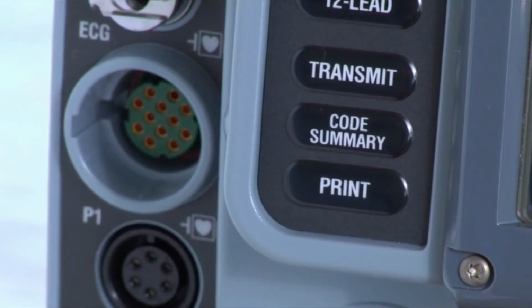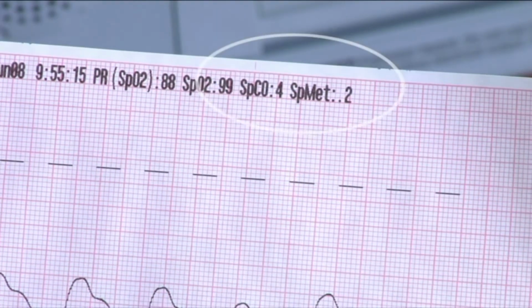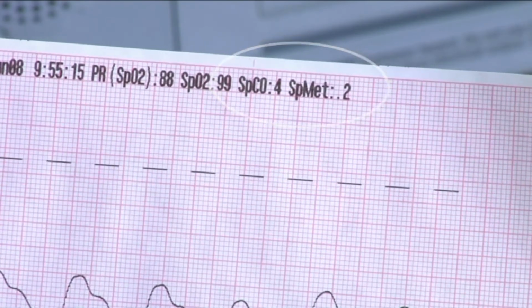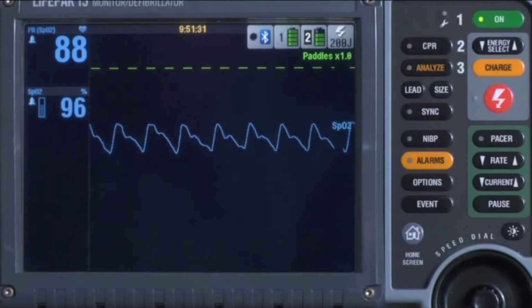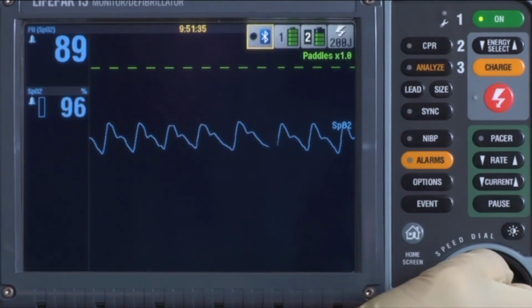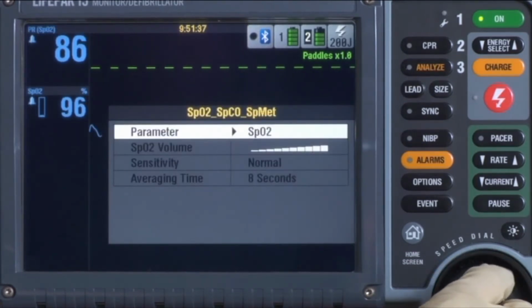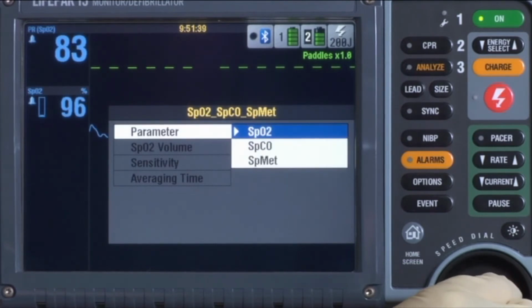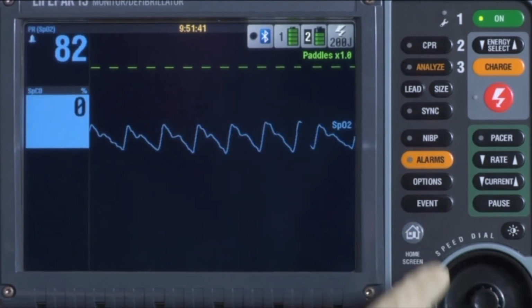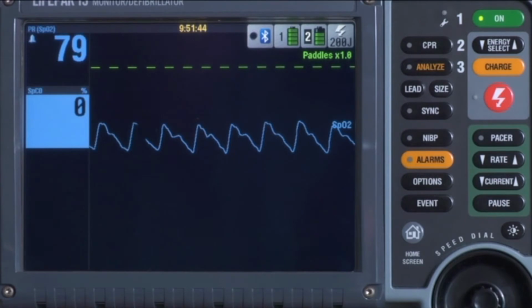But if you want to check those actual readings, there are two ways to do it. You can press print and get a printout of the vital signs. You see the CO and MET values up here on the strip. Or you can manually display the value in the SpO2 area. Rotate the speed dial to outline the SpO2 area and press it. Select Parameter from the menu and then select SPCO or MET. The value displays for 10 seconds, then reverts to SpO2.